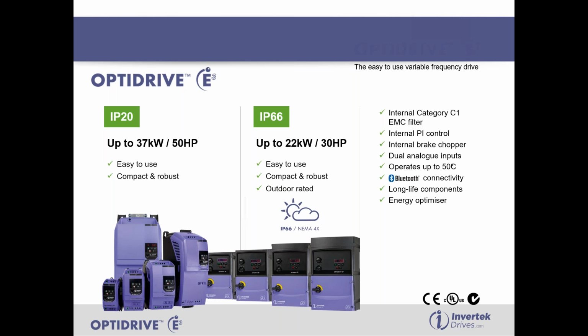We've got Bluetooth connectivity with the drives. So we've got a little module we can plug into the communication port on the drive, and we can connect directly to the laptop with OptiTools. And as part of the reliability of these drives, we also use long life components. So there's only 2 components in VFDs that wear out over time, and that is usually the DC bus capacitors, because that's their nature, and the cooling fans, because they are obviously rotating machines.